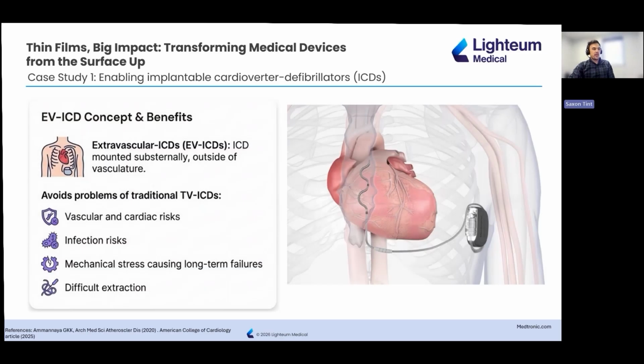And this is where thin films is quietly becoming one of several key enabling technologies. These high charge injection coatings, like titanium nitride we just looked at, they make these electrodes so sensitive and efficient that they can reliably sense and stimulate the heart without being inside it. This wasn't possible before. A major milestone came in October 23 when the first EV ICD was approved by the FDA. It's a really great example of how advances in surface engineering, they don't just improve devices, they enable entirely new device architectures.